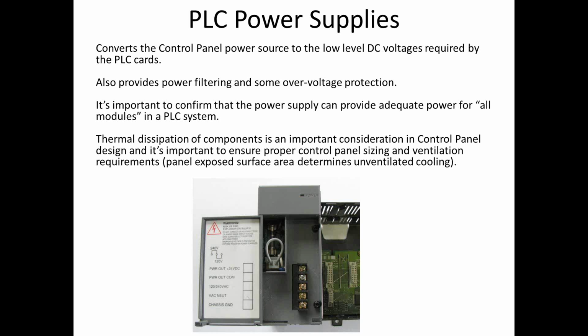What it does is it takes the power that you plug into, and it converts that down to a low-level voltage that a lot of the PLC cards require. It also helps filter out some of the noise in the electrical current, and it protects against overvoltage. Overvoltage isn't good for the cards, so it's important. One thing to realize is that the cards and the power supply both can generate a lot of heat, and you need to be aware of that when you're constructing a control panel and finding out what the design is. You want to make sure it's designed to ensure proper ventilation and that you are aware of the thermal dissipation of the components.